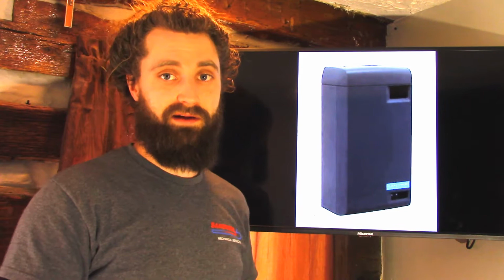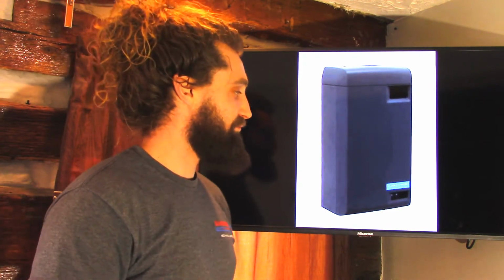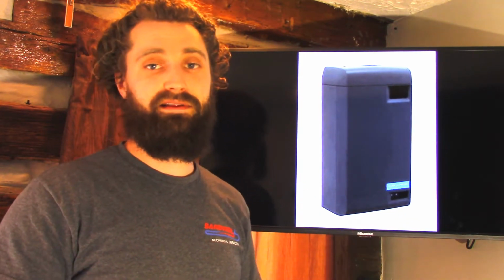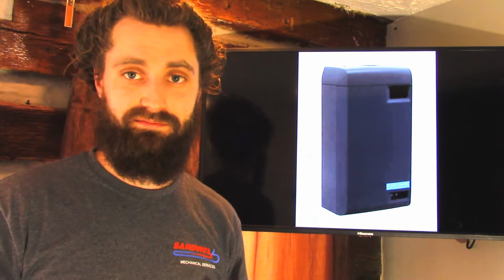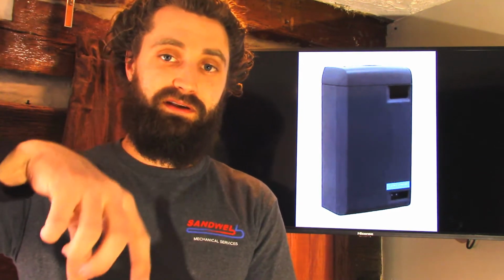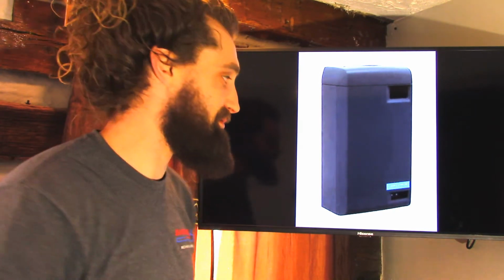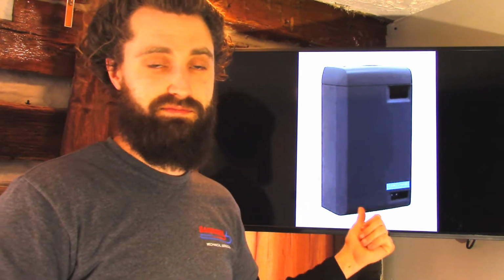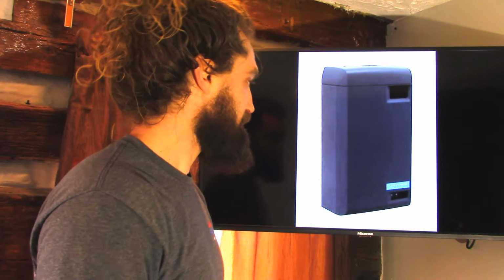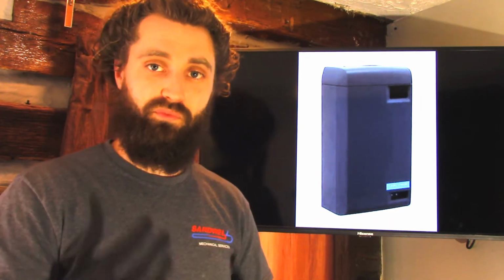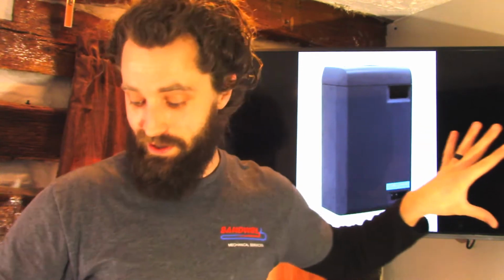Now, the thing with these is they're about double the price of a bypass humidifier. The big thing with these is that if you don't have good water going into them, they're going to clog up, they're going to fail. There's a bunch of sensors in there that get calcium deposits on them. The heating element will just get corroded with calcium. I've seen a lot of issues with not necessarily this brand, but all of the brands. So a lot of the manufacturers have really worked out some of these bugs, but that's something to be mindful of. We're talking a steam humidifier, which is 2 times the price of a traditional bypass humidifier, but then we also need to put some sort of water conditioning in line with this so that we're feeding it nice, clean water, at minimum filtered water, so that that's not an issue.